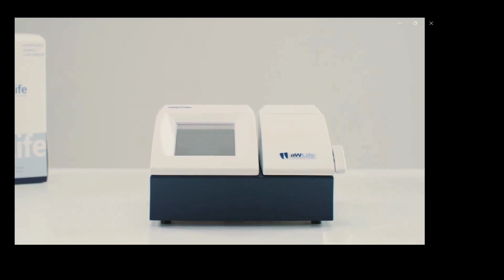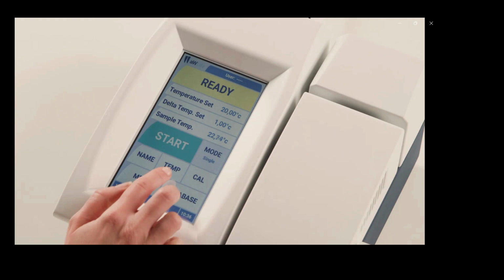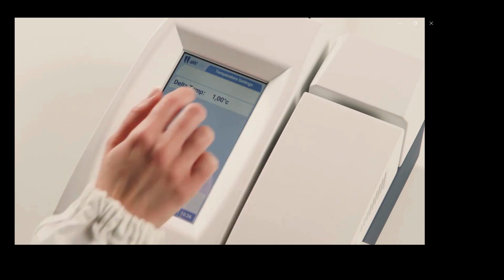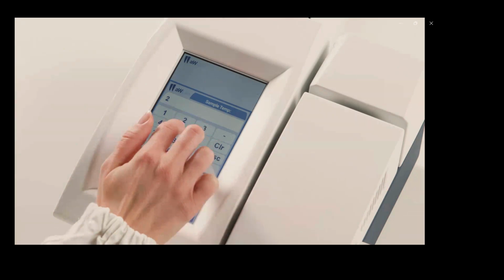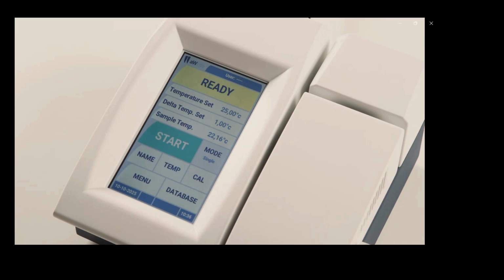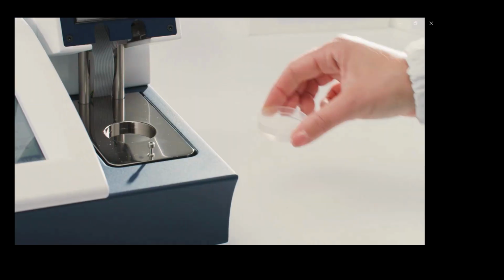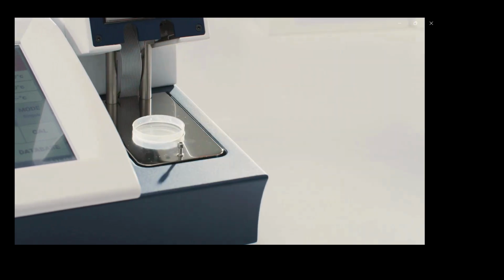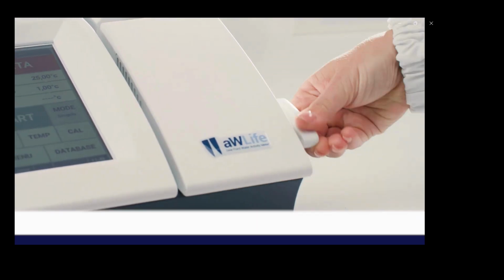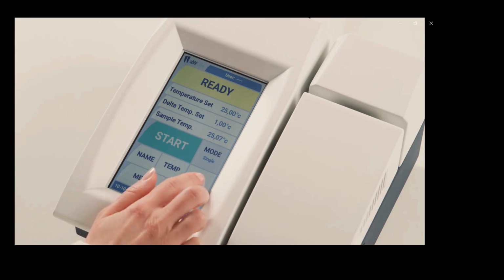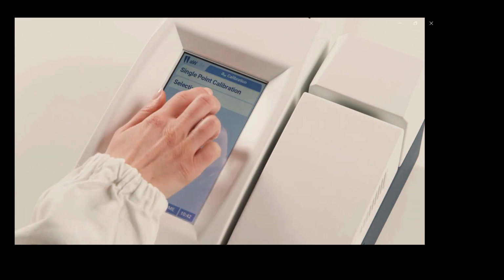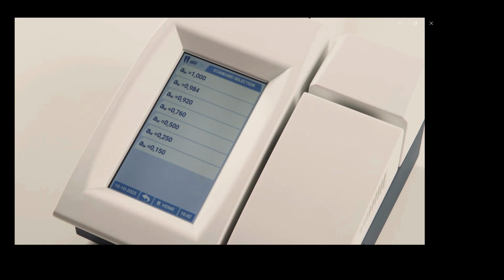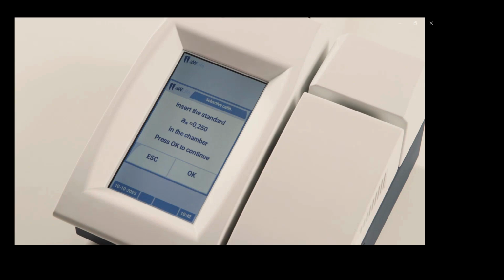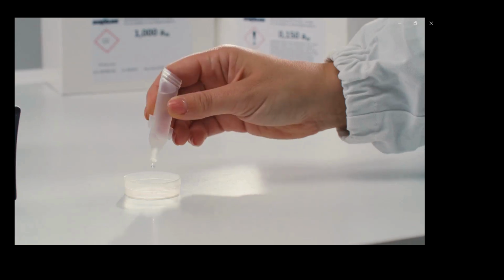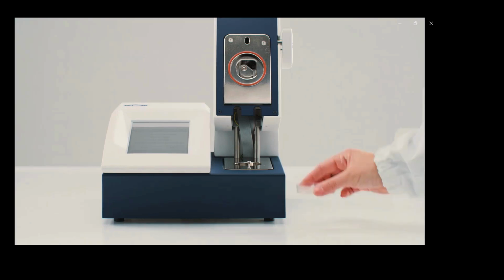Before proceeding, set the working temperature of the analysis chamber. The standard temperature is 25 degrees Celsius with a tolerance of plus or minus 1 degree. This means the instrument can start the analysis with the sample temperature between 24 degrees and 26 degrees Celsius. The instrument will automatically bring the sample to the correct temperature. Step 2. Calibration. Before each session, it is necessary to perform calibration by selecting the calibration type. The software will display all available standards to choose from. Next, place the selected standard in the analysis chamber and confirm to start calibration.